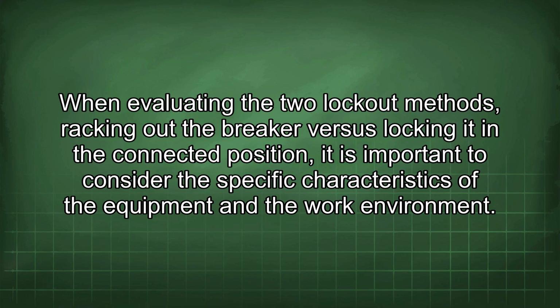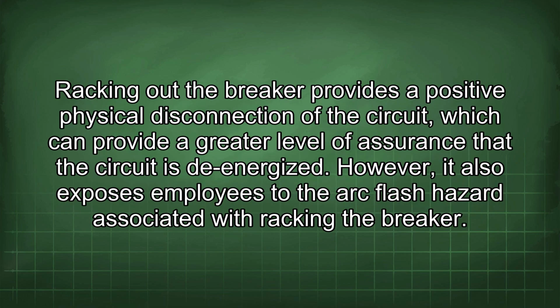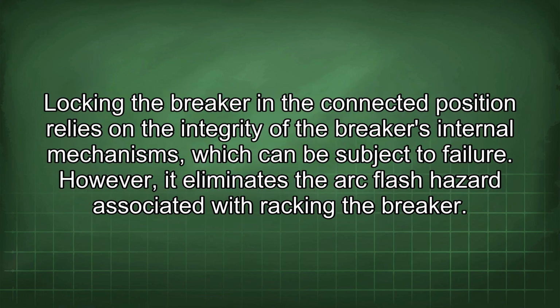When evaluating the two lockout methods, racking out the breaker versus locking it in the connected position, it is important to consider the specific characteristics of the equipment and the work environment. Racking out the breaker provides a positive physical disconnection of the circuit, which can provide a greater level of assurance that the circuit is de-energized. However, it also exposes employees to the arc flash hazard associated with racking the breaker. Locking the breaker in the connected position relies on the integrity of the breaker's internal mechanisms, which can be subject to failure. However, it eliminates the arc flash hazard associated with racking the breaker.